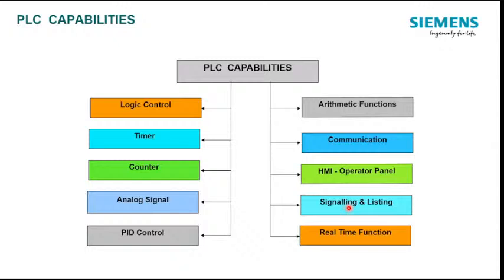So when we have this kind of signals, more than 1,000 or something, it will be very difficult to monitor whether it has been happening sequentially. So in that case, when we are using the PLC, we can very easily monitor whether I am getting inputs and whether my outputs are being operated as per the sequence of my operations. So the signaling and listing of the inputs and outputs can be easily done.